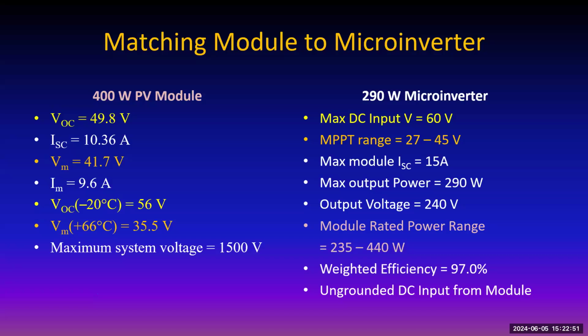Well, on a cold day, that open circuit voltage could go as high as 55, but it's still well within the 60 volt limit, so the yellow match is okay. Also, the low temperature open circuit voltage could go 56. So yeah, that's fine. We're good. 60 makes it just fine. If we look at the white one, the short circuit current, how does that match up? Well, 10.36 for the module, and the microinverter allows 15, so we're good there too.